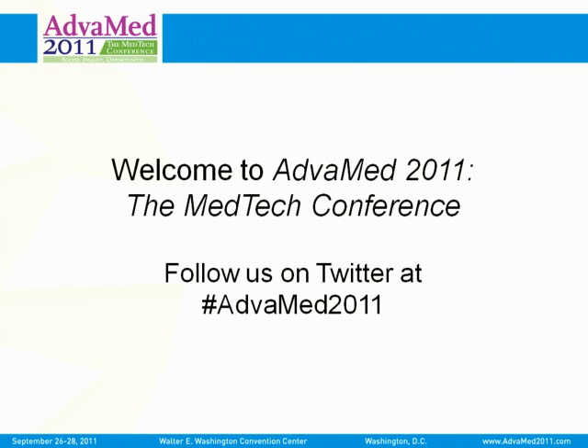And that's true what Judy was saying, that TGA in Australia has already presented a new IVD regulation. In this, they are presenting 4 classes. They're calling them 1 to 4, and this classification is A to D. And they are giving some examples of the parameters and which class they feel these parameters belong to. So it can be interesting for you to see what TGA has made with this classification, but for sure it will be more complicated for a manufacturer. And maybe the notified body too, but...